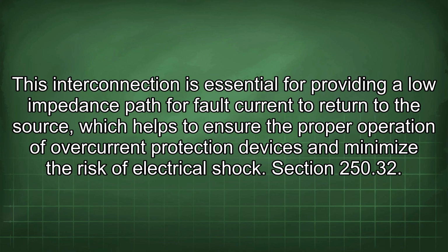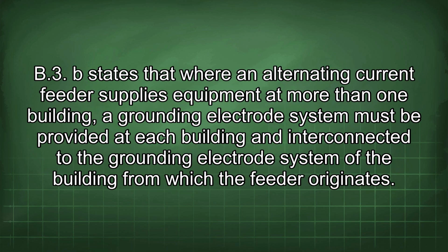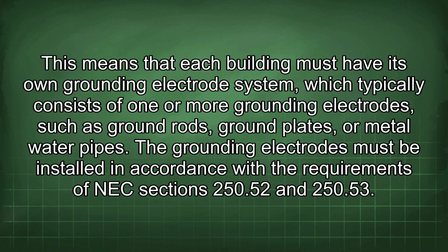Section 250.32 B3 B states that where an alternating current feeder supplies equipment at more than one building, a grounding electrode system must be provided at each building and interconnected to the grounding electrode system of the building from which the feeder originates. This means that each building must have its own grounding electrode system, which typically consists of one or more grounding electrodes, such as ground rods, ground plates, or metal water pipes. The grounding electrodes must be installed in accordance with the requirements of NEC sections 250.52 and 250.53.